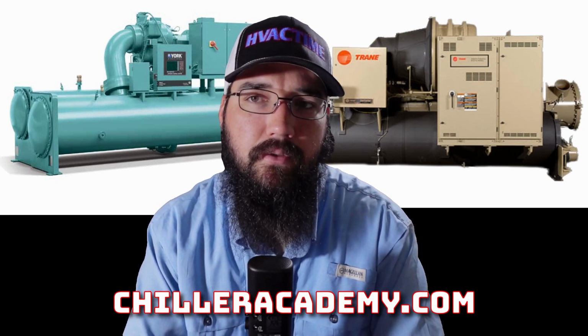This is part of what makes low pressure machines a little more challenging. With high pressure, unless there was an egregious error, dealing with non-condensables isn't that big of an issue, but when you get into low pressure, having to address non-condensable problems is a big issue, and it's something we deal with a lot. Purge systems that aren't functioning and cause surging conditions are something we deal with a lot. The whole point of the purge is to remove atmosphere, and I'll have a whole lesson dedicated just to talk about purge systems.